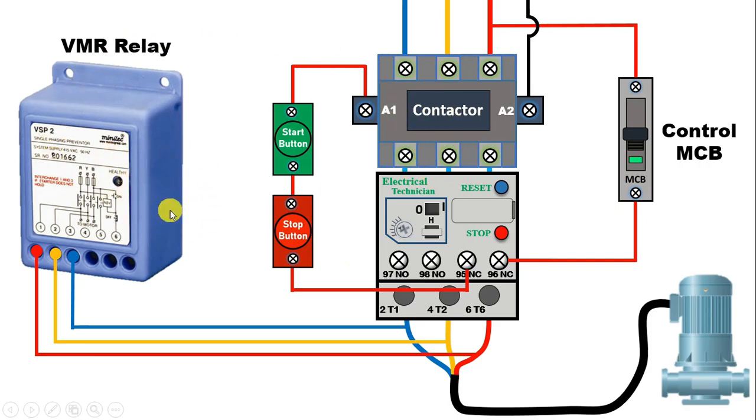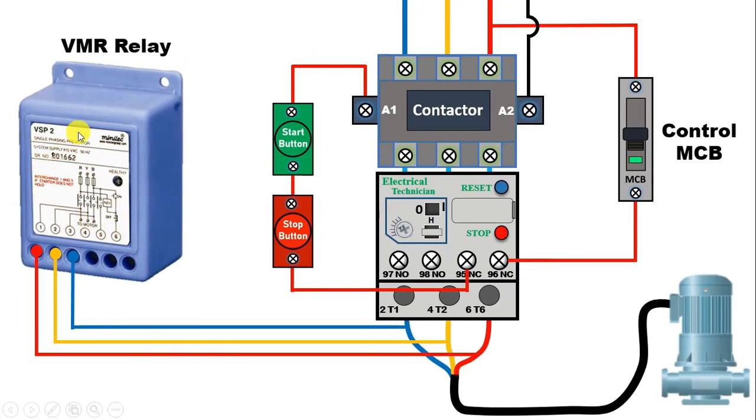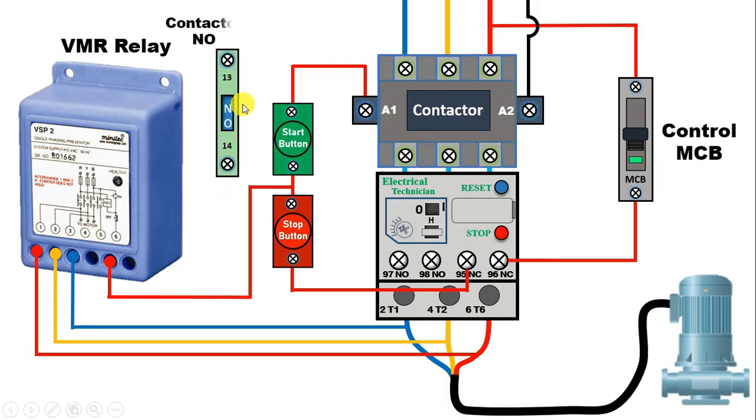But still, the connection of the VMR relay is left. For this, what you have to do — the holding circuit we have, with this holding circuit, we have to use the auxiliary contact of this relay. In this VMR relay, terminal numbers 5 and 6 are the NO contact. This ANO contact needs to be used. With the output terminal of the stop push button, connect one wire and connect the other end directly with terminal number 5. From terminal number 6, power will be supplied to the NO terminal of this contactor. With this 6 number terminal, connect one wire and provide input supply to the NO contact of the contactor. From the output terminal of the NO contact, connect one wire with the output of the start push button. So this circuit is the holding circuit, and the NO contact of the VMR relay is connected in series with it.